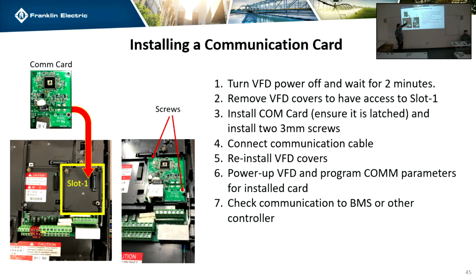So basically just kind of lightly put it over there, get it all leveled up and push down. It snaps right into place. You'll have 2 screws that mount it in, and that's it. Once you do that, you power up the drive, go into the COM parameters, and make sure that the drive will automatically detect it. You want to make sure it detected it. And then you can go in and do all your setup if needed. For Bluetooth, all the setup's going to be on your phone. And then the Ethernet, there's not really a lot of setup. You just plug and play and go.